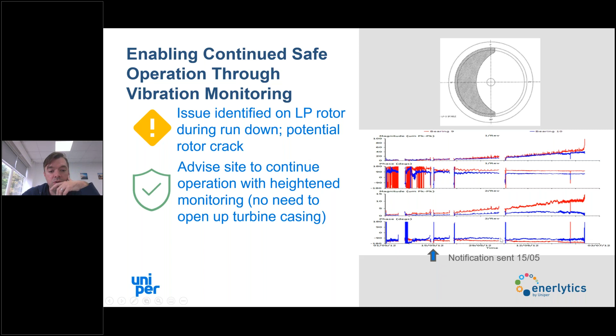And you can see here the levels starting to creep up, all within the ISO guidelines, and we had heightened monitoring to enable them to do that in a safe manner. Then that was opened up just before the beginning of July. The scale ends on the 3rd, so 1st of July or last day of June. And when they did the RCA and they cut through the rotor, there was in fact a crack in the rotor. So we've enabled them to continue to safely operate, get the revenue from the market, and avoid a catastrophic failure.